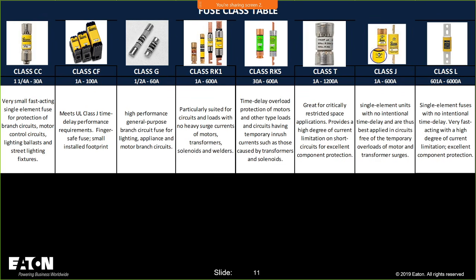And the big question you should have in your mind is, how do I know which fuse to use? And hey, that rhymed. We can make a song. You have to understand the characteristics. For me, the time current characteristic curve is the determining factor. If you look at any one of these examples, like the CC, a very small, fast-acting single-element fuse for protection of branch circuits, motor control circuits, lighting ballasts, they may be fast-acting, but they've got to have some sort of delay in there to be able to be used on those circuits. And the trip curve should reflect that. And we're going to hopefully look at one of those trip curves.